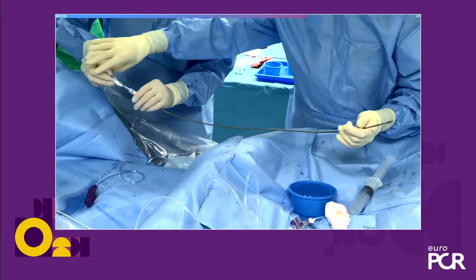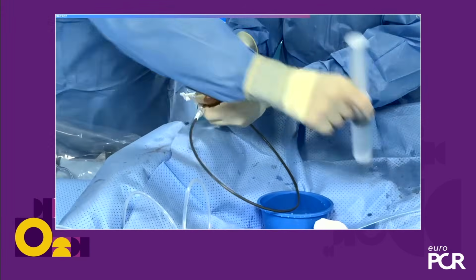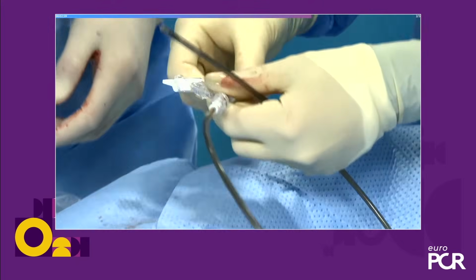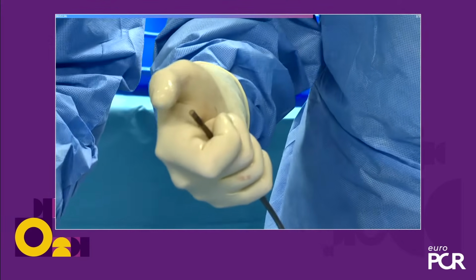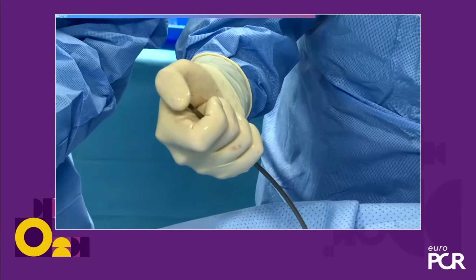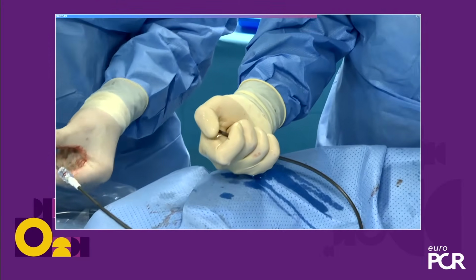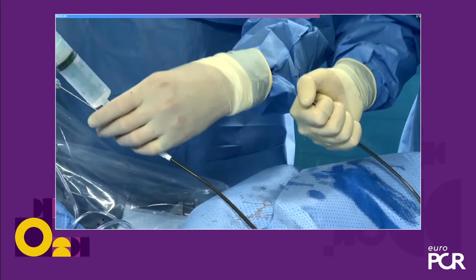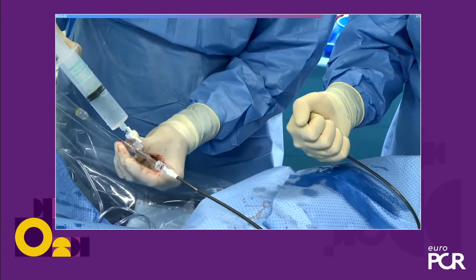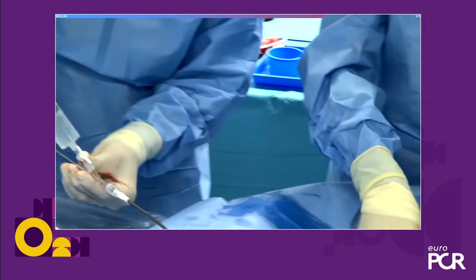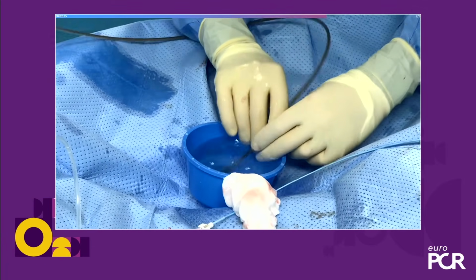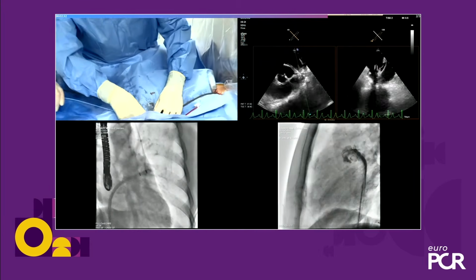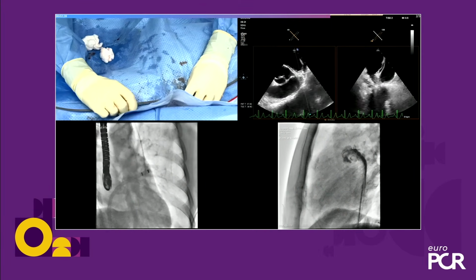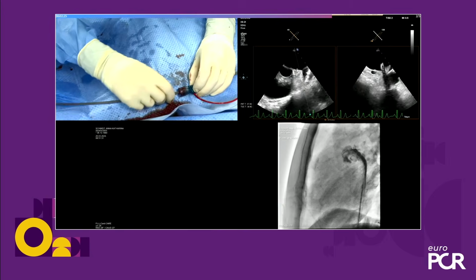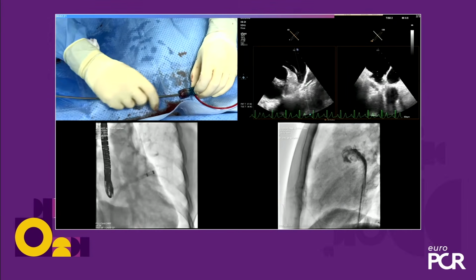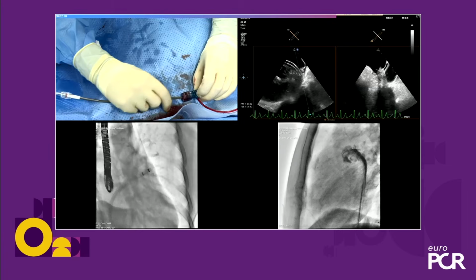So for the device, we actually move a bit back and forth and then align it with the marker. Then flush first the Y piece. We obstruct and flush it back. Maybe we have to move again a bit. Yeah. We flush the Y piece and then we flush antegrade a few times back and forth so that we avoid bubbles in the system. So what we do now is we open the sheath, the valve, and flush and enter and close again. That's really the nice thing about the Watchman sheath, that there is absolutely no risk for air embolization.